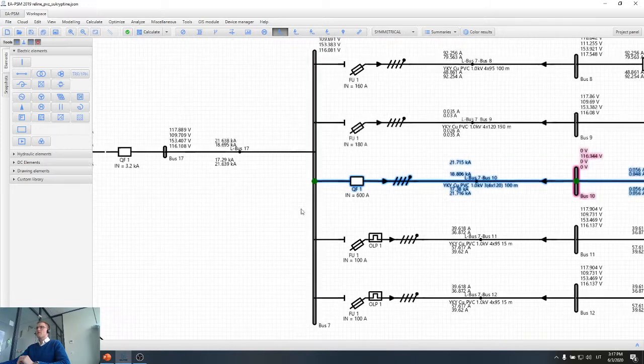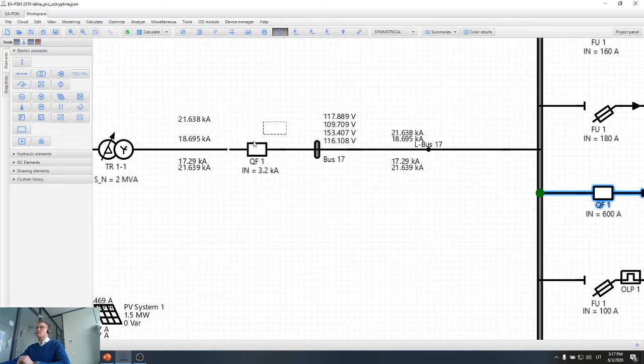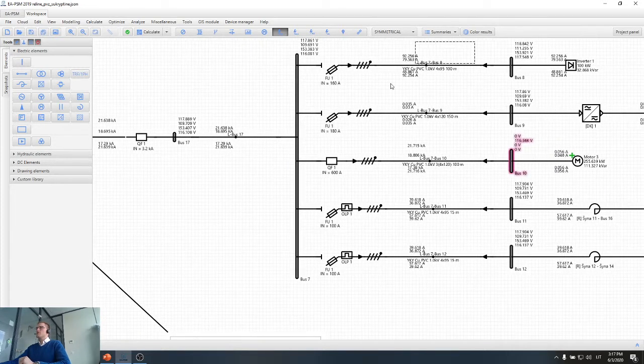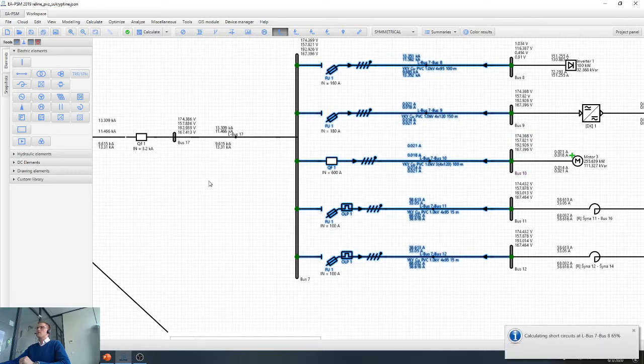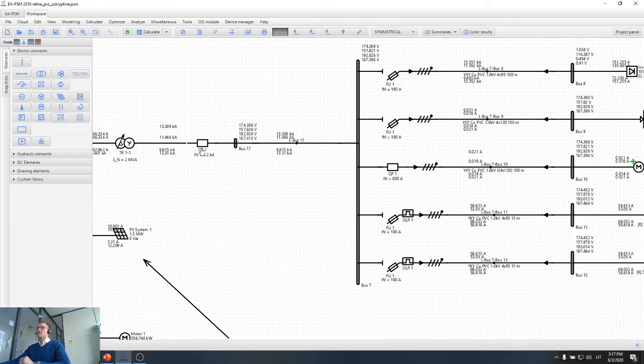And in this kind of network, if we go further on, we can see that there is one more breaker, which is on the feeder of the section here. So this breaker is actually working as a backup protection for all the protections here. These fuses, breakers, overload protections are protecting the cables, and the backup protection is here. So basically, if there is some problem with any of these protection devices, we hope that this one will work. So this is the reliability of protection devices, which is again a very important principle.